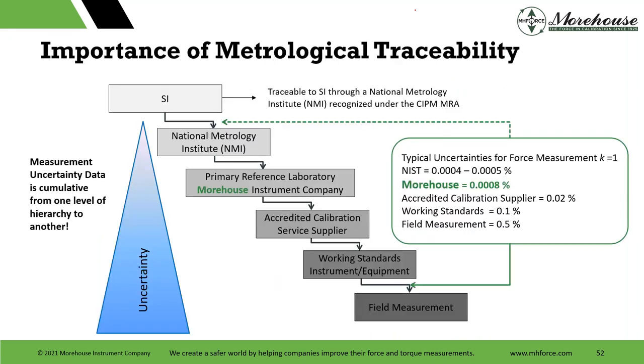A lot easier to show it, I think, this way. We start, wow, we're starting pretty far down, right? You start with traceability, which basically is a documented unbroken chain of calibrations, each contributing to the measurement uncertainty. It starts at the SI, we're traceable back to the SI unit. Typically, most labs like us, reference labs, are sending equipment to NIST, or having our dead weights calibrated directly by NIST. And then that's going to propagate the uncertainty down to us, however good NIST can do.